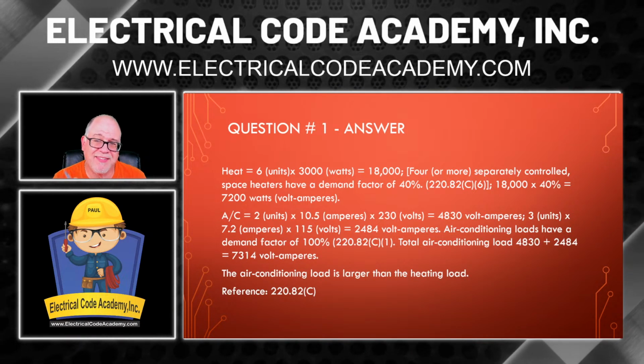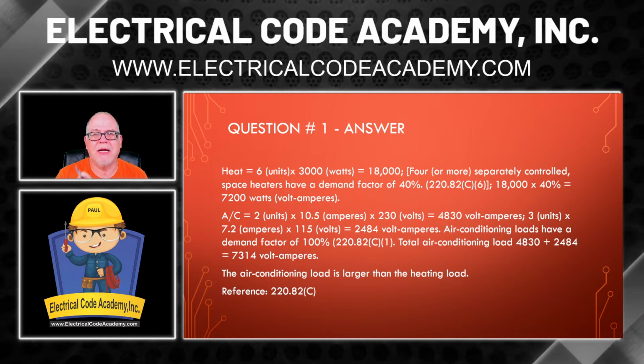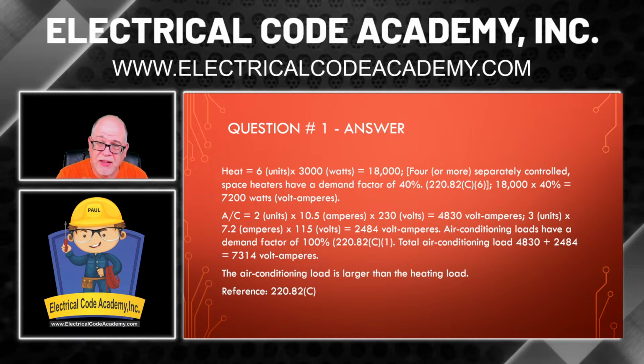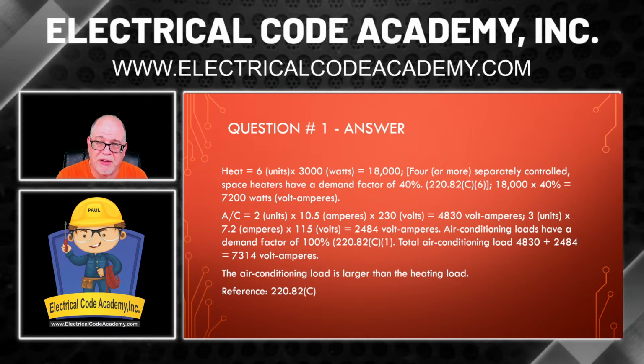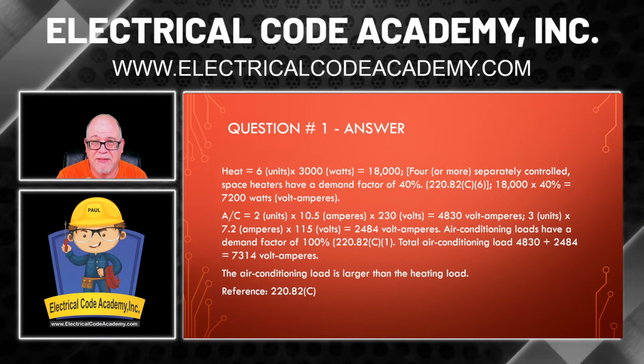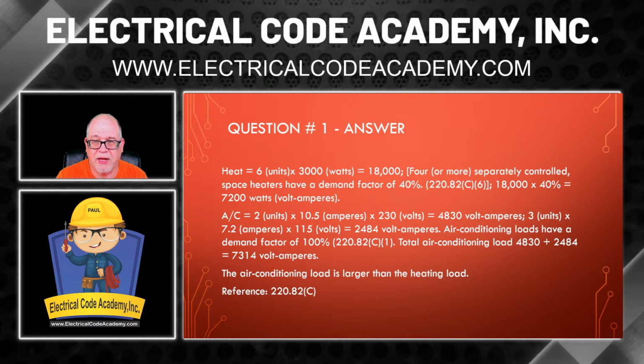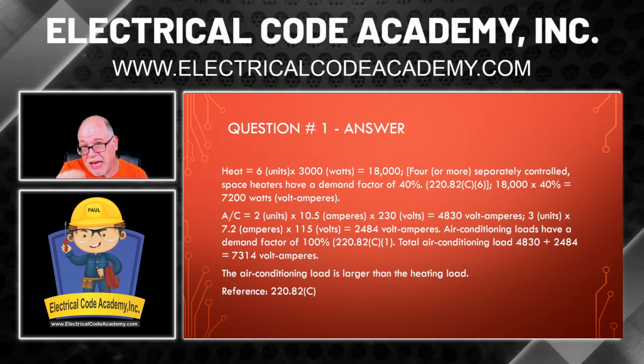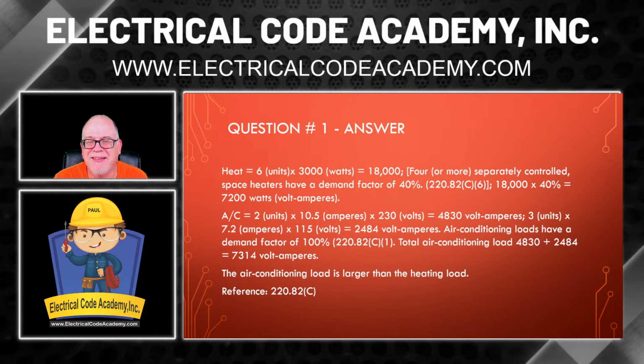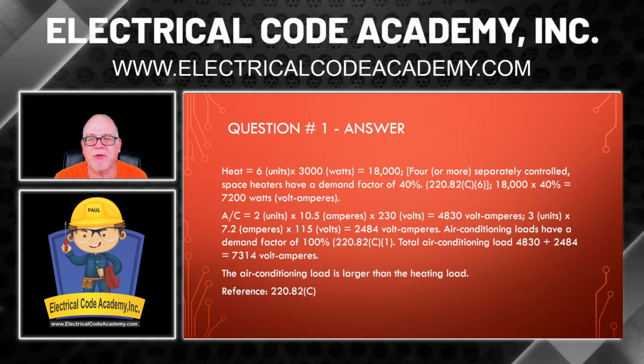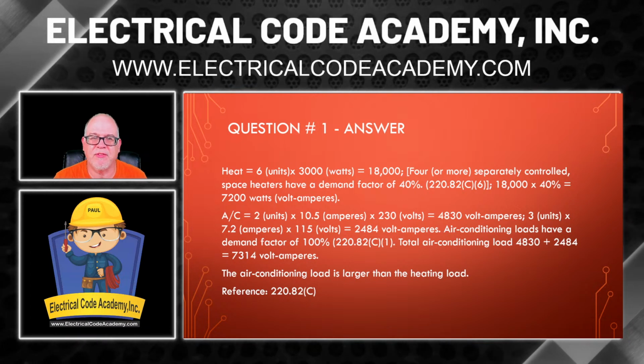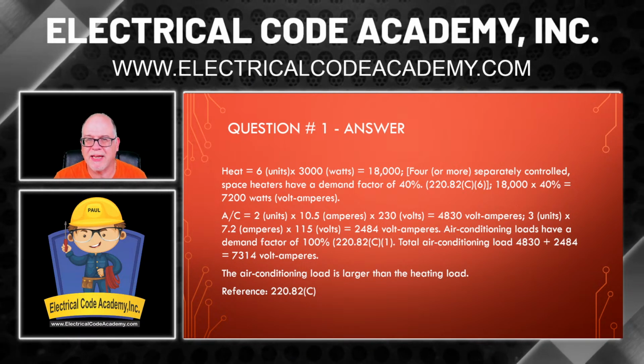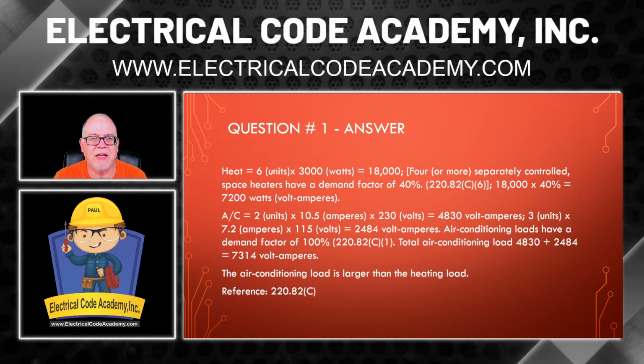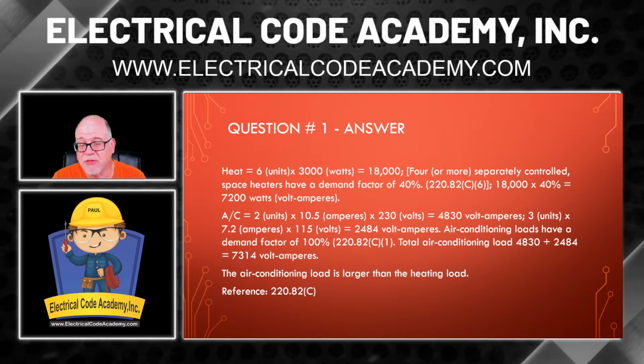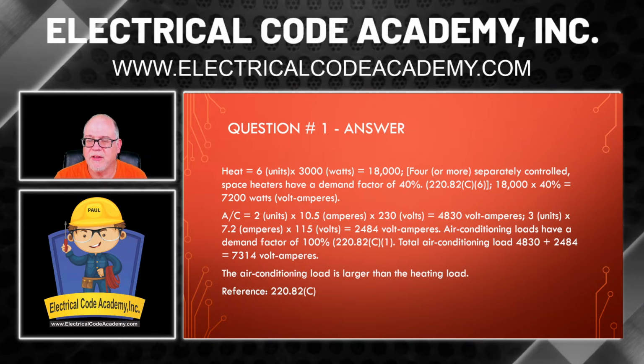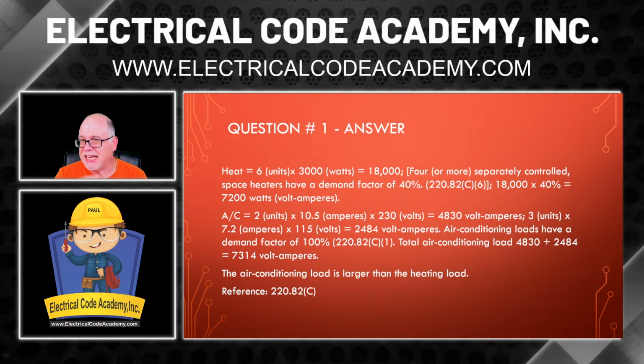Now, remember what it said? It says that we take what? Now, this says 220.82C6, but it's actually, which one was it? It was 5 that we're using for the heat. Okay, so typo. So we're doing 18,000, and we're going to multiply that by 40%. That gives us 7.2 kW, or in our case, since we worked it out in watts, it is 7,200 watts, or 7,200 VA.